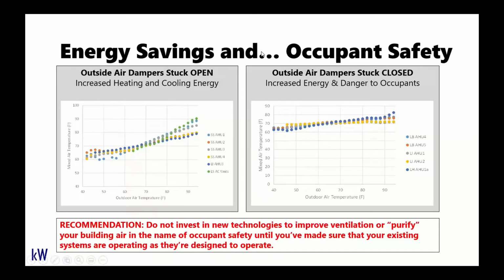And the last one I really want to talk about in detail here, and it's especially important these days, I think, is the component of occupant safety, as well as energy savings benefit. So here we have a graph on the left of the outside air dampers of a few of the air handlers at student services and library and life sciences at Citrus College. This graph indicates that these outside air dampers are stuck open. So we can see that as the outside air temperature changes, the mixed air temperature is changing in exactly a linear fashion with that outside air temperature, which means that no air is recirculating back from the zone, and it's just a fully 100% outside air unit.